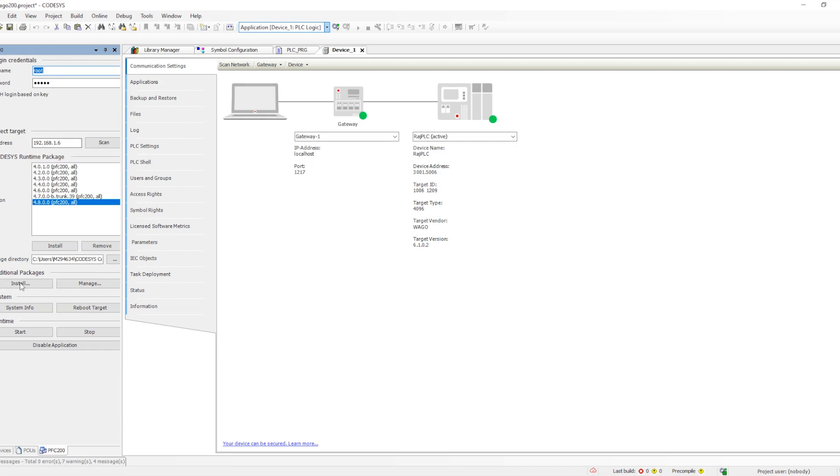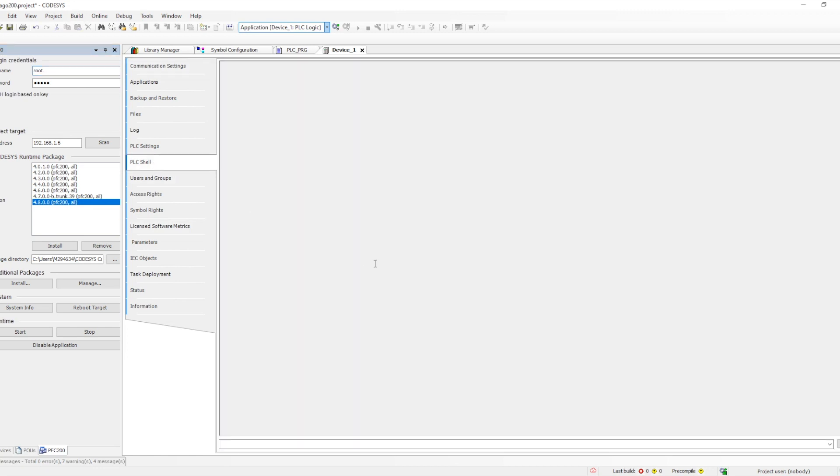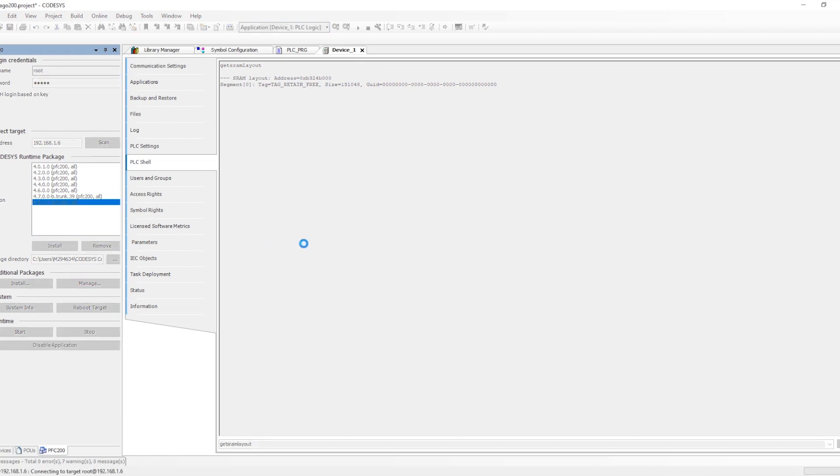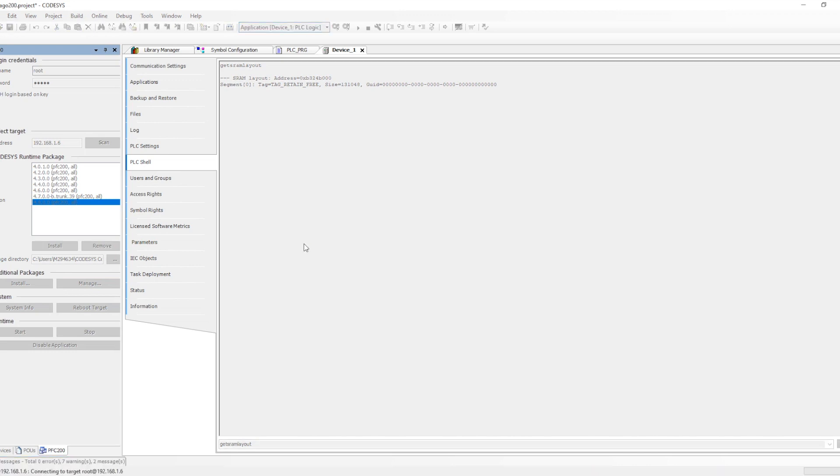In order to install the Codesys runtime we need to go to the update PFC 200 and then we will get this option. We need to provide root login password and then we need to click on the install button. We need to select the version which we need to install and it will start installing this runtime into the PLC. It will take some time to get it installed.